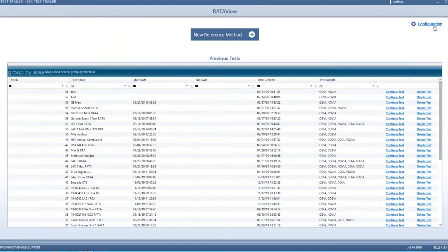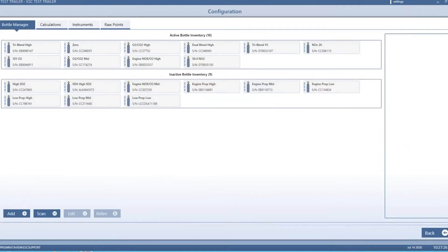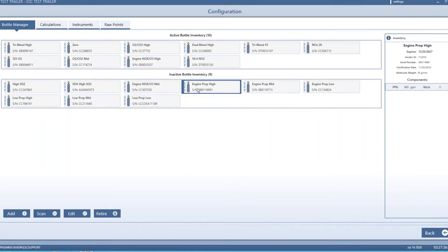I'll start with the configuration menu. Before running a RATA test you'll want to make sure all your bottles are set up correctly and all your instruments are on the right IO and reading correctly. There are four main tabs in the configuration. The bottle manager tab has two main panes: active bottle inventory and inactive bottle inventory. You can choose which bottles are active and inactive, and drag an inactive one up to the active list — a way to filter which bottles you have on hand that day and which will appear in your drop-down selection boxes.